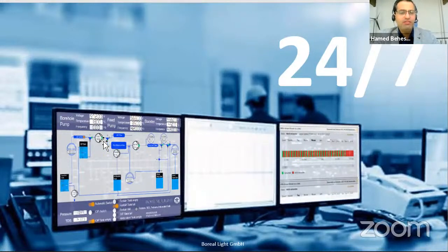The position of every valve is clear here by color. The valves that are open now are green; if not open, the valve goes gray. The temperature, the RPM—the illiterate operator just needs to see what is happening. If the tank is full or half full, it's orange. If there is any malfunctioning or problem, the point turns red, with a red circle around the exact source of the problem, whether it's water quality, pressure, temperature, hertz, or voltage.